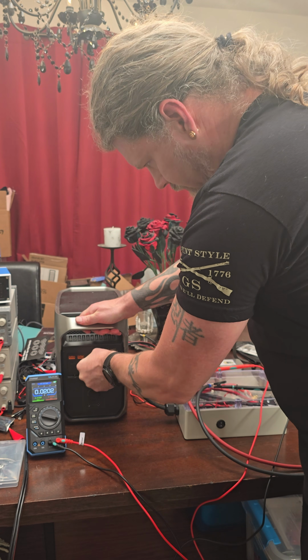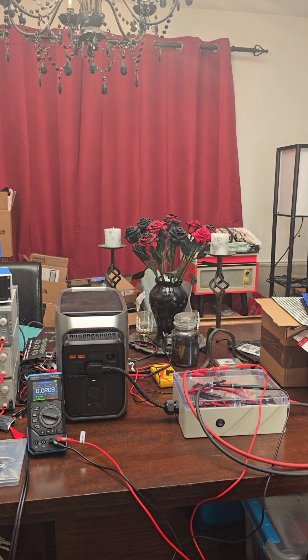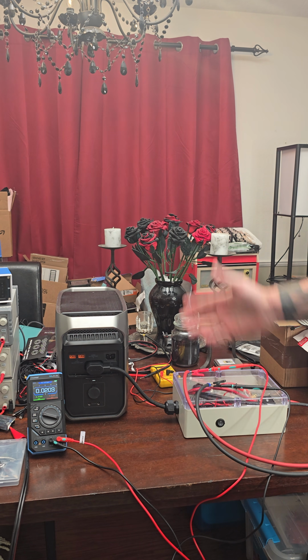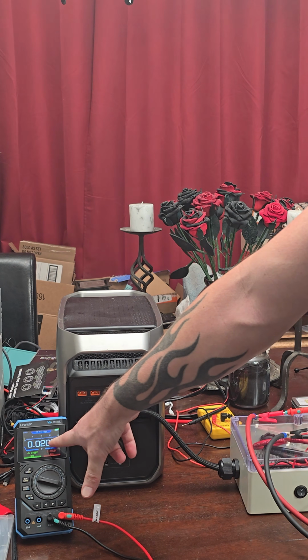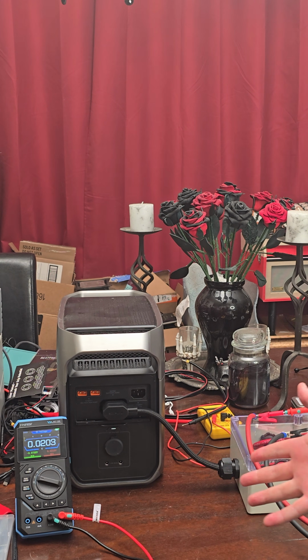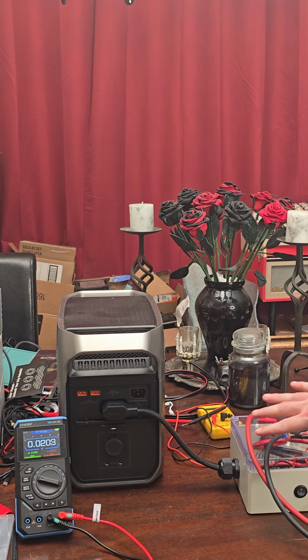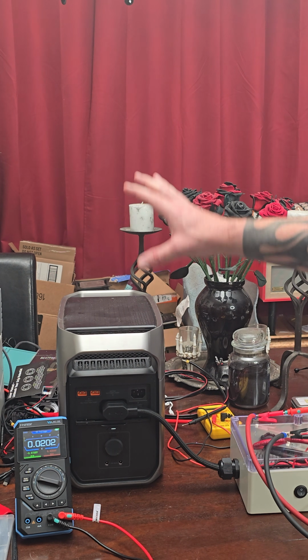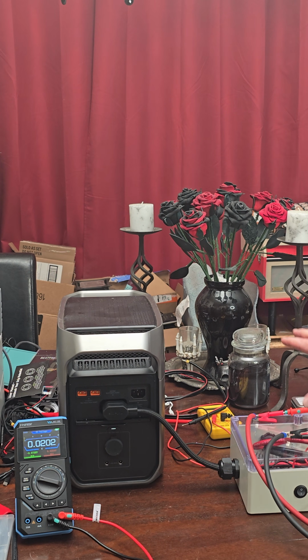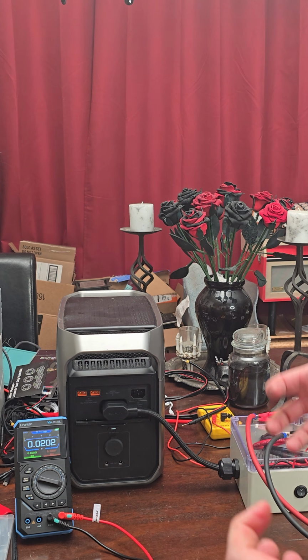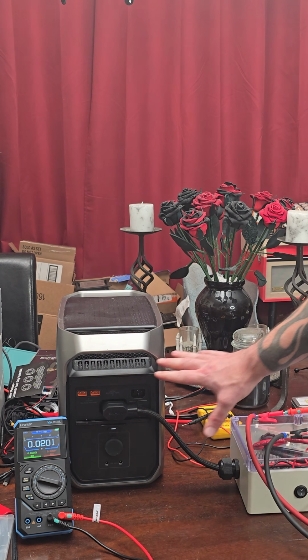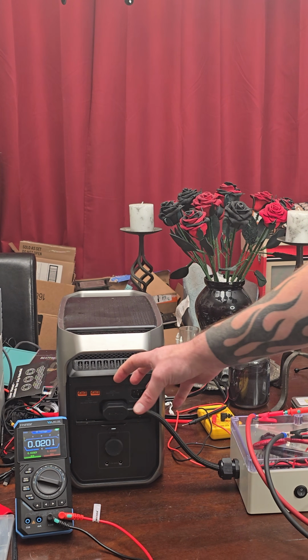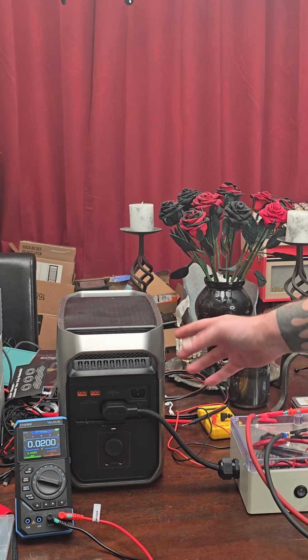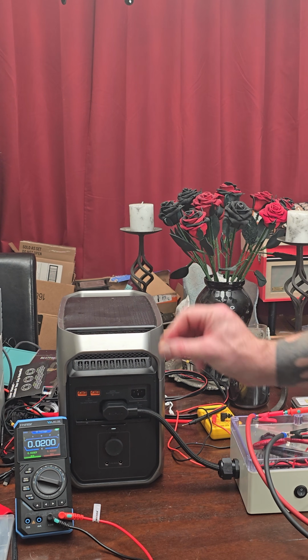So, a nice fit. And just like that, you would think maybe it's not working. Well, you see we do have some minor voltage. You could literally touch this with your fingers, you can touch anything inside this box. The whole point of doing it this way is it's safe. There's no arcing hazard, there's no electrocution hazard. We're using the OEM built-in features with the BMS to not activate our power until we actually want it. And now we don't have to switch high power through like a relay, we're just doing very small data wires.